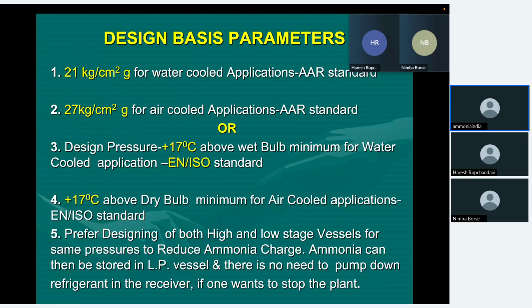Now, when we start designing pressure vessels, the first question that comes up is: at what pressure do we design it? The standard as per our IS standard is 21 kg per centimeter square for water cooled applications and 27 kg for air cooled applications. But if you go to the EN standard or ISO standard, they also suggest that you can design the pressure vessels for 17 degrees above wet bulb temperature if it is a water cooled application, or 17 degrees above dry bulb temperature if it is an air cooled application. Of course, for ammonia plants, air cooled applications are comparatively less than 5%. Most of the applications are water cooled applications.